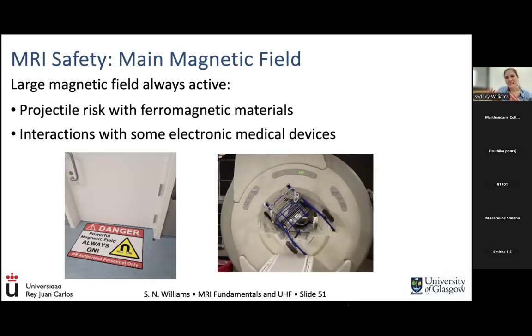So the biggest thing to consider with MRI safety is that this is a very, very strong magnet. It's measured in field strengths of Tesla. A Tesla is 10 to the fourth Gauss, and the main magnetic field of the Earth is a few Gauss or less. So it's a very, very strong magnet, even in relation to the strength of the Earth's magnetic field. Because of that, you always have to be wary of bringing in any ferromagnetic materials. All things going into the MRI environment should have some sort of labeling stating whether they're acceptable to be there. Some are conditional, some are absolutely not, and some are safe.